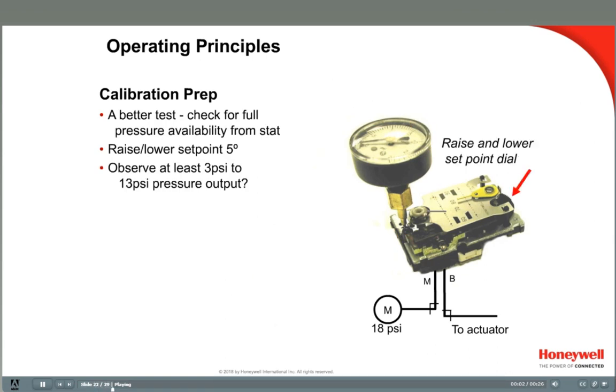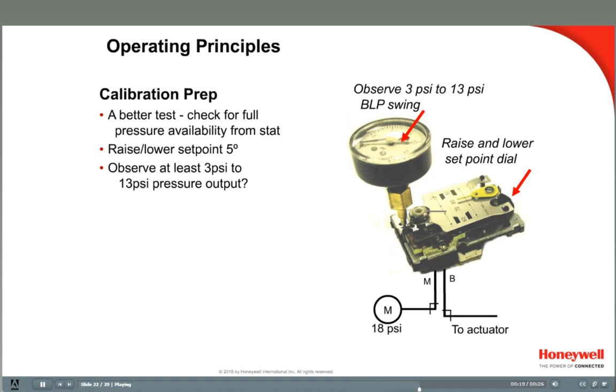A better operational check will determine if the thermostat can produce a full branch pressure output. Insert your branch line tap gauge and then turn the set point knob at least 5 degrees high and then 5 degrees low from where it was set. Verify that the branch line pressure can rise and fall at least from 3 to 13 pounds. If not, the stat may be defective and cannot be calibrated, or there may not be sufficient main air pressure.